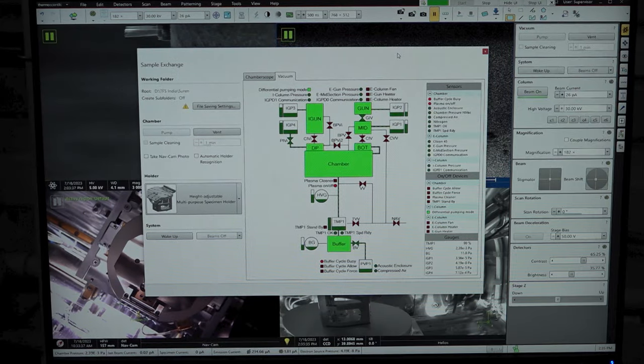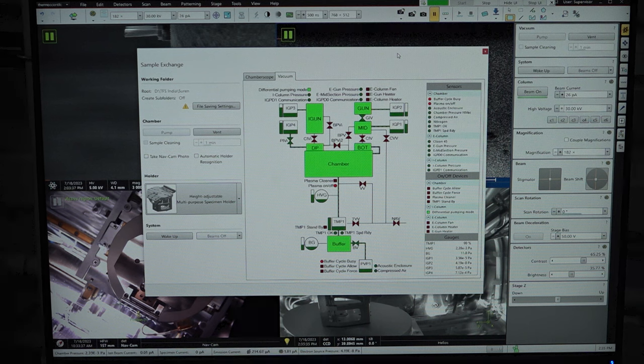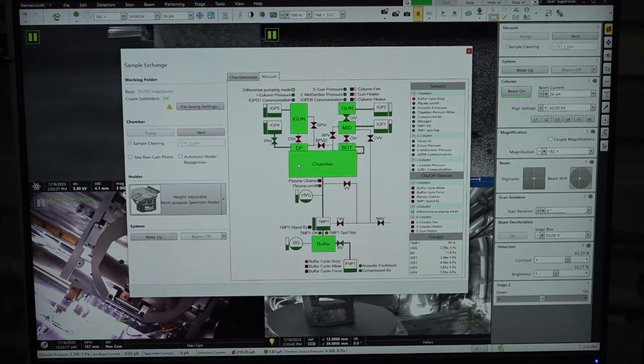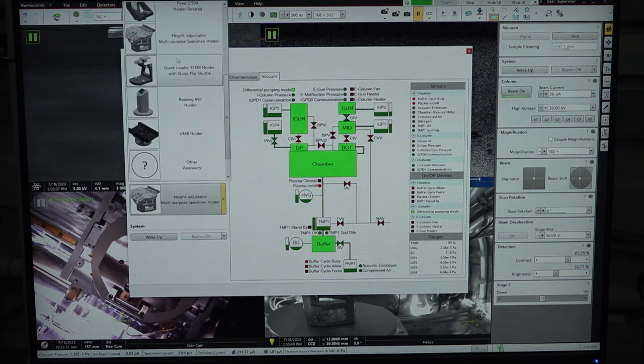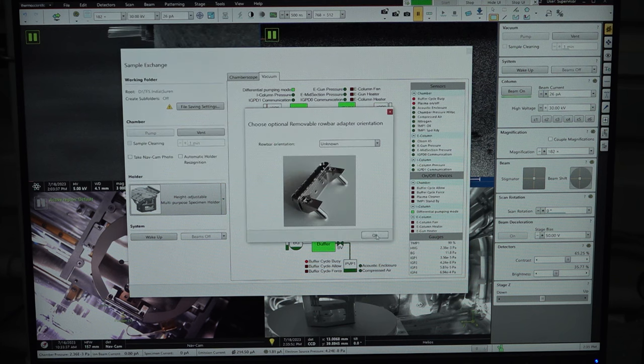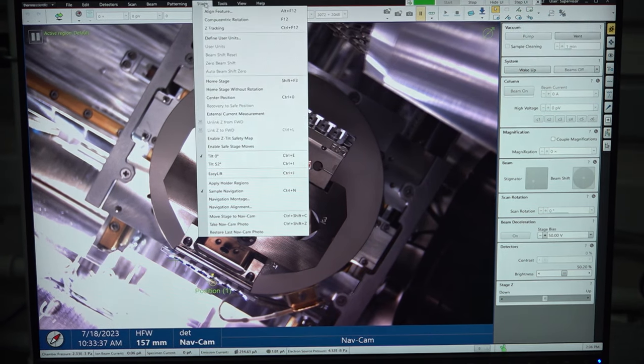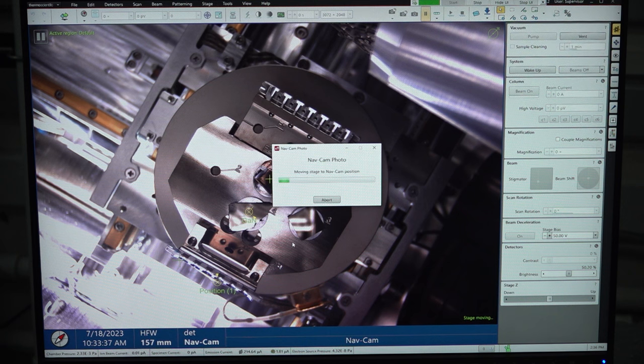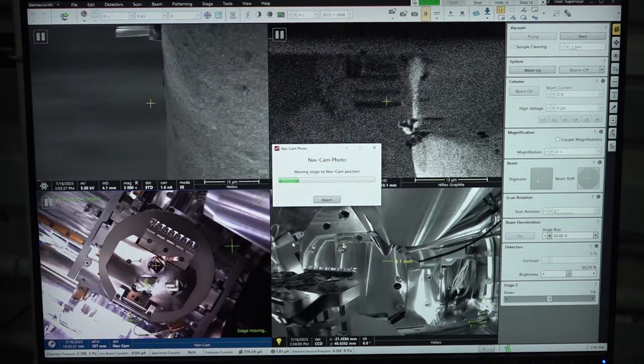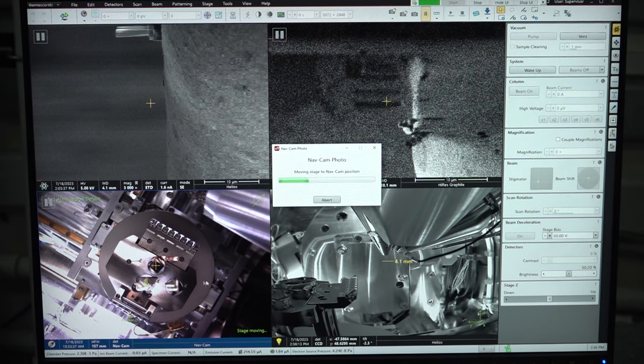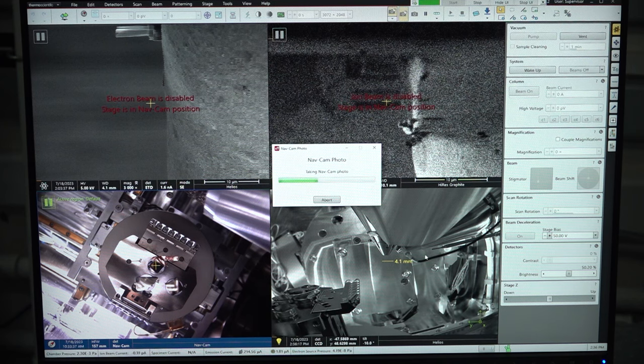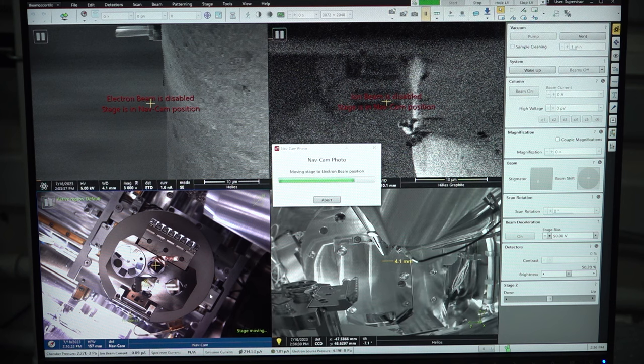Now let us look at the experiments. We have loaded the sample into the vacuum chamber, and the chamber has sufficient vacuum to operate. Let us choose the holder first — we will choose the height adjustable multipurpose specimen holder. The next step is to capture the navigation picture. Let us go to the stage option and take a photo of the current image in the chamber. The stage will move to a specific location to capture the photograph.